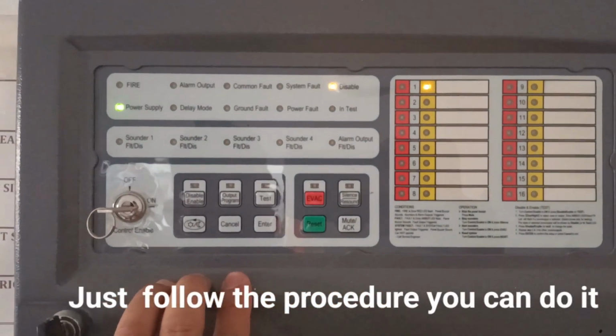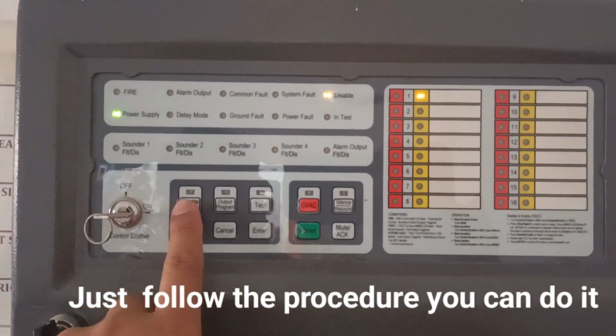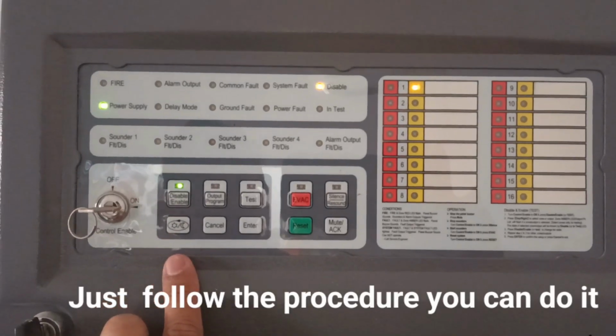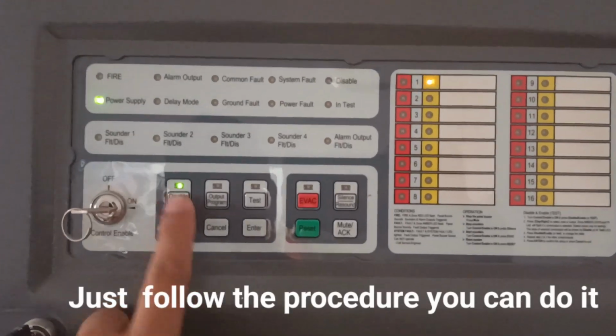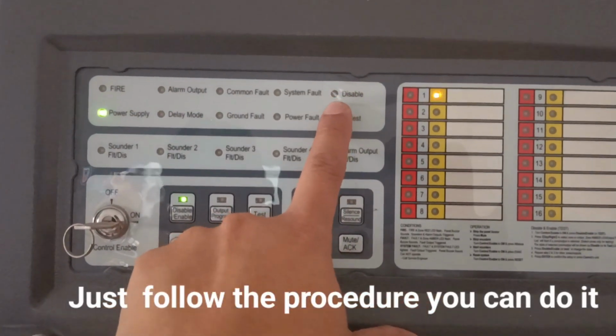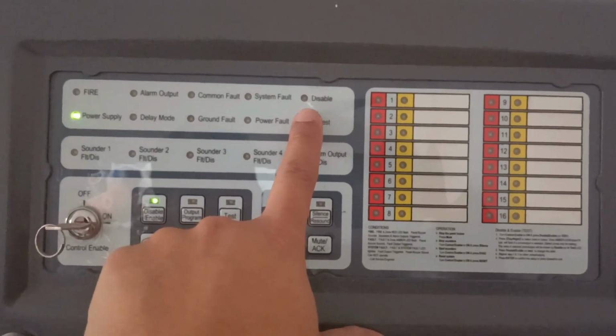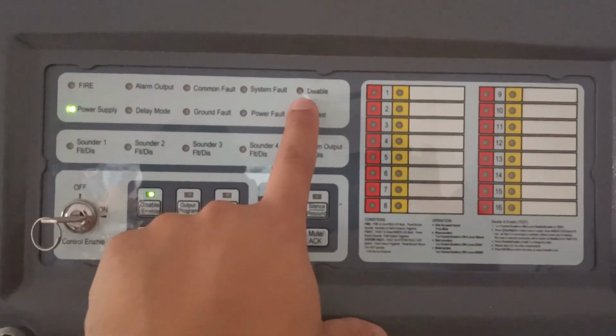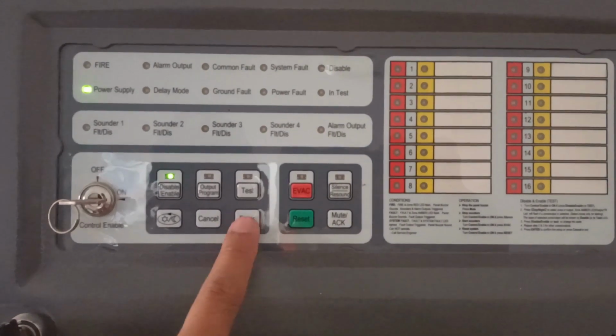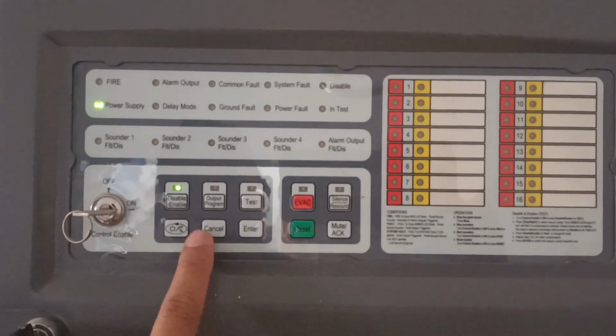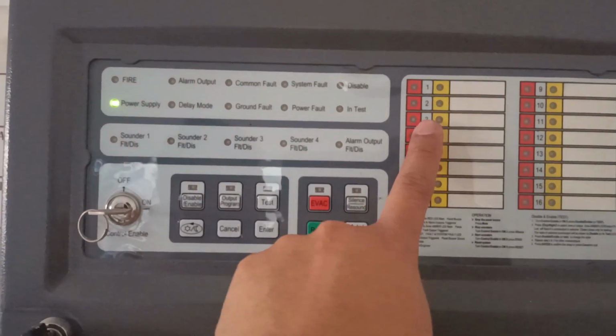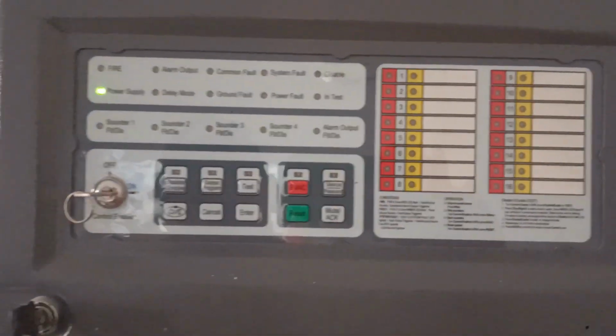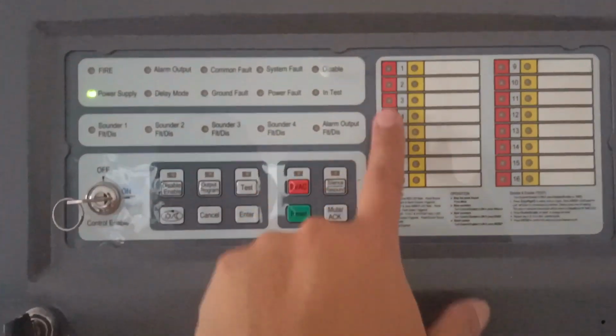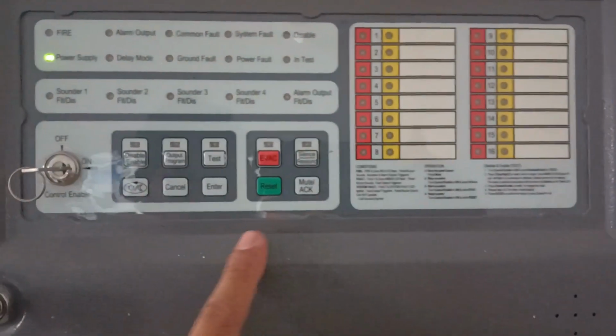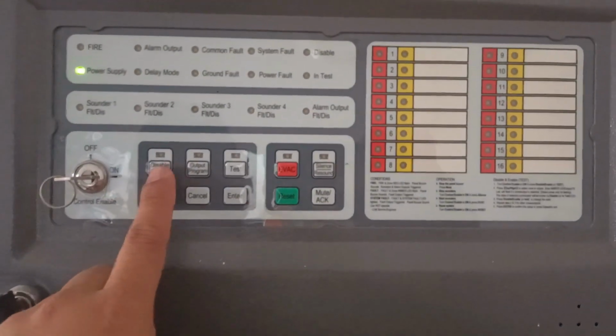So if you want to enable, you press disable and press disable again. So the disable light, the yellow color, is gone. So you press enter, then cancel. So the disable is already cleared, and zone one is enabled.